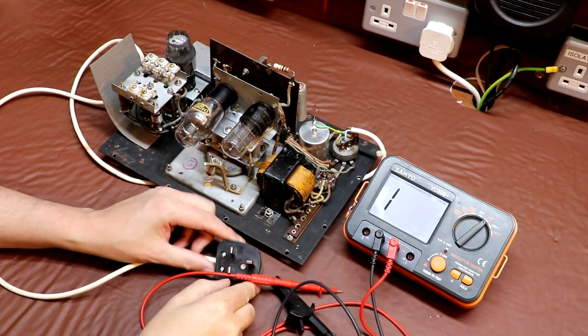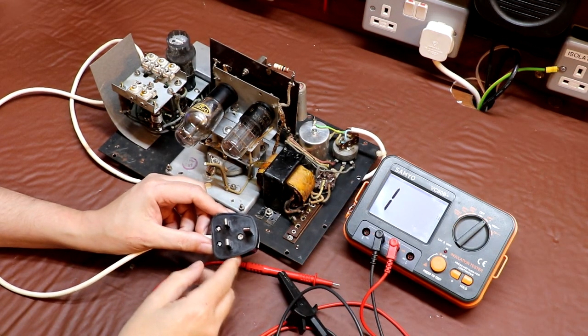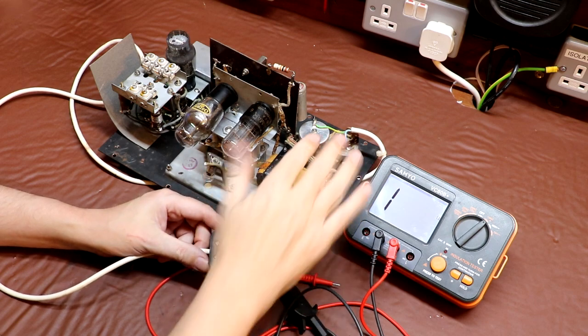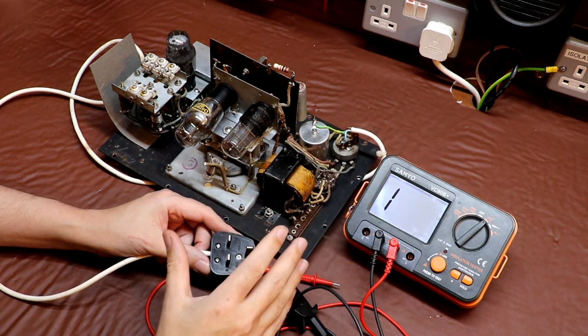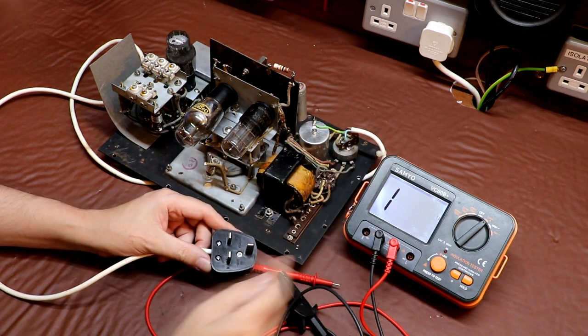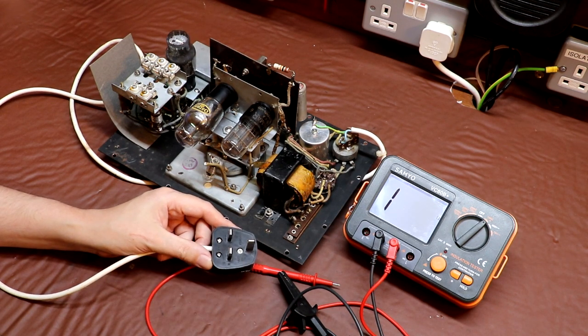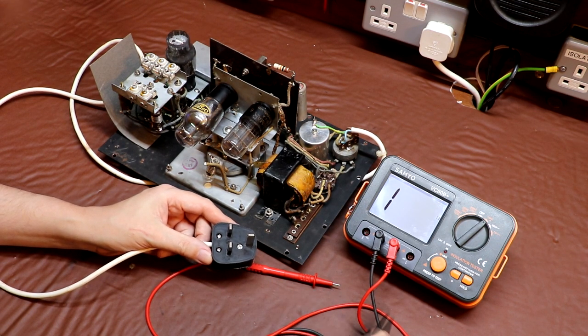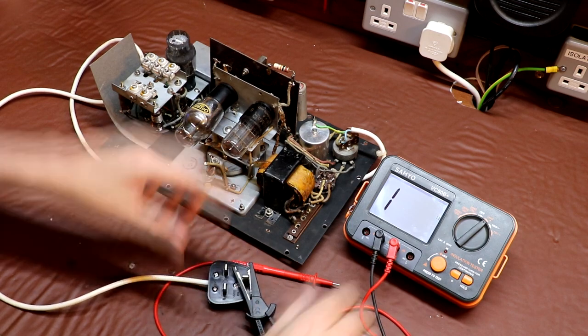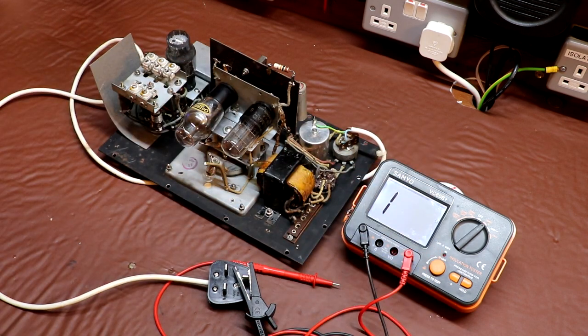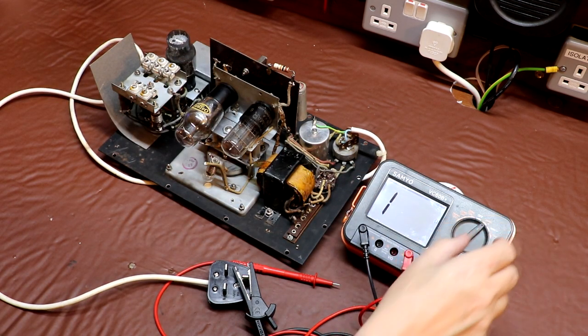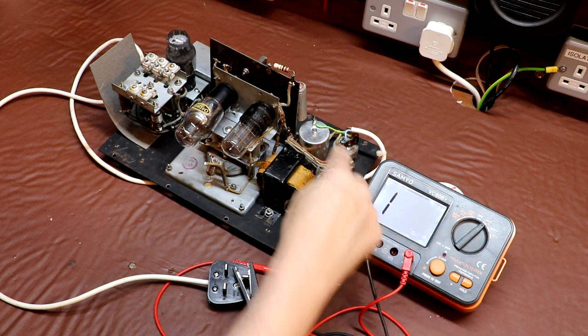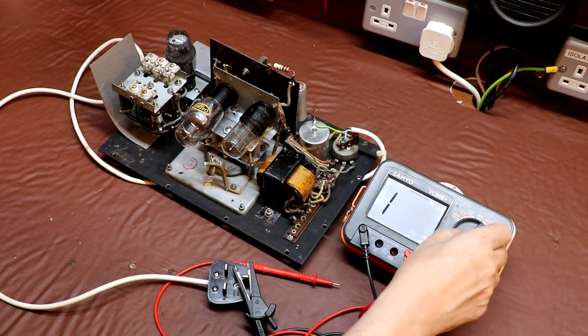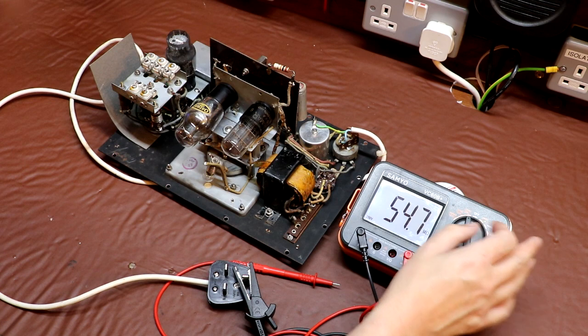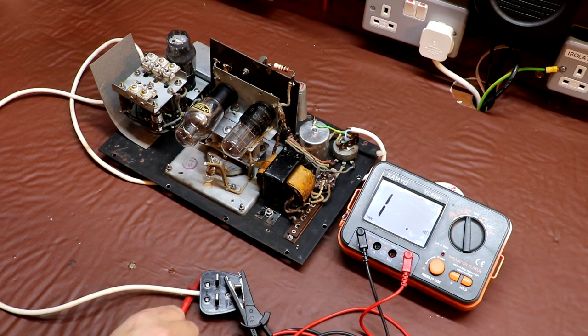And finally, the next test that I'm going to do is insulation resistance. And basically what I'm checking here is that none of the live parts are actually in contact with the chassis. So we have no leakage between the live and neutral and an earth. And the way we actually do that is I take my clip lead here of my insulation meter. I do have to just move the leads over to put this into the insulation range. And I'm going to do the test here at 250 volts, because I'm a little bit concerned about these microcapacitors in our filter. I don't want to put too much voltage across them, so I'm going to go to 250 volts on there. So these probes are now live.